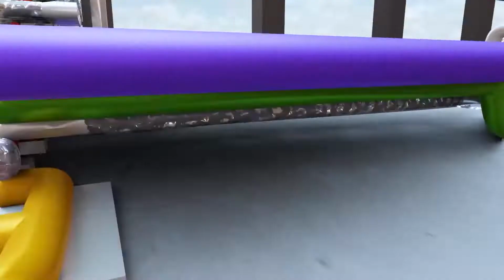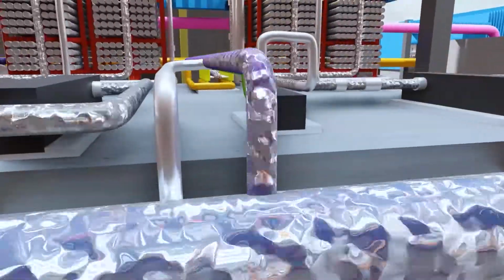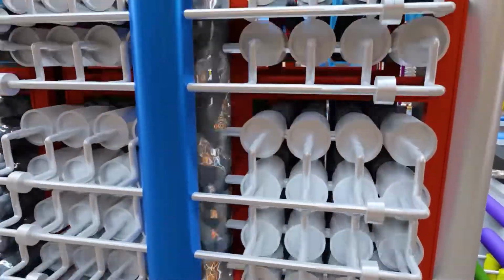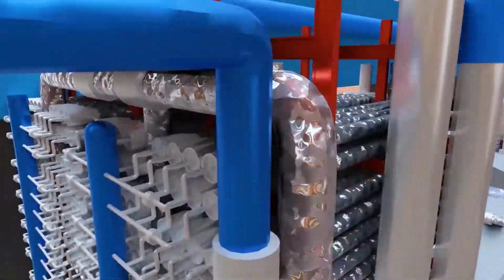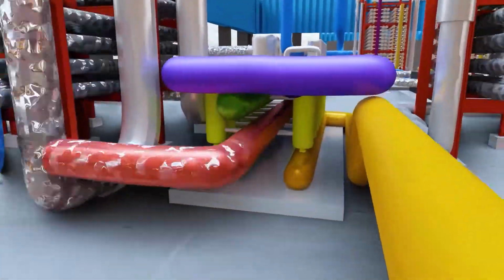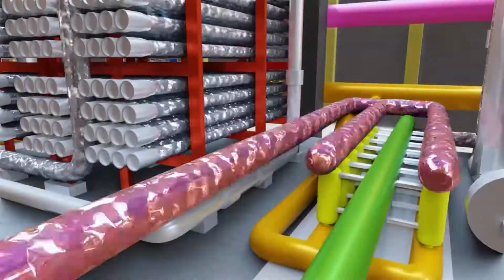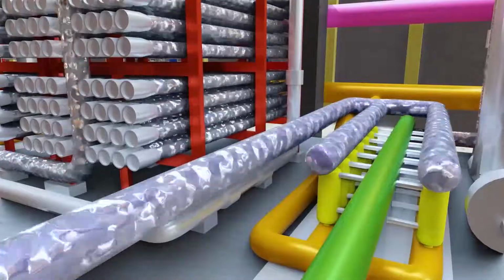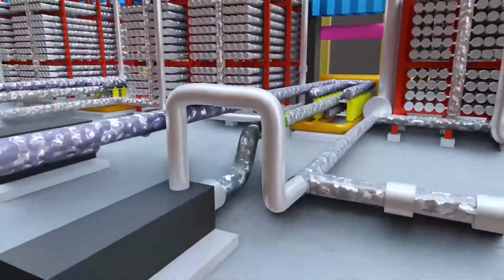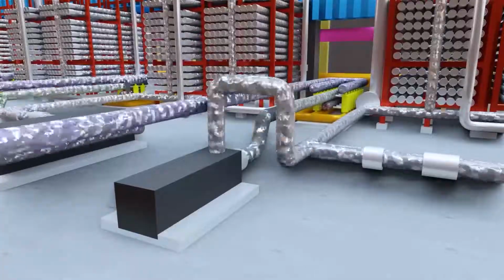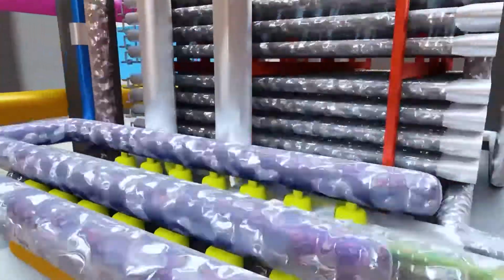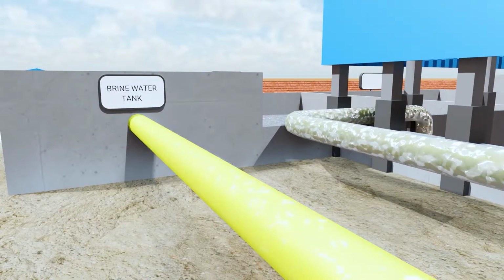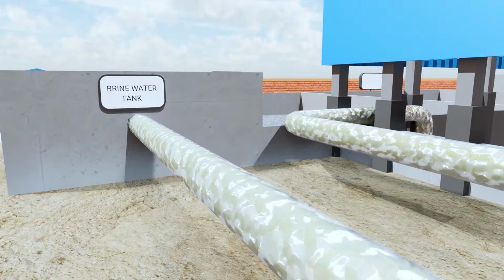The service water from the inlet header will enter into the energy recovery device with low pressure. The reject water of the reverse osmosis pressure will flow through the back of the device. The pressure exchanger will transfer the high pressure of reject water to the feed water. As a result, the pressure of feed water will increase and the pressure of reject water will decrease. A booster pump is provided to maintain the pressure loss from the pressure exchanger. The service water with the help of a high pressure pump will move into the inlet of RO skid and the reject water with low pressure will be disposed back to the brine water tank.